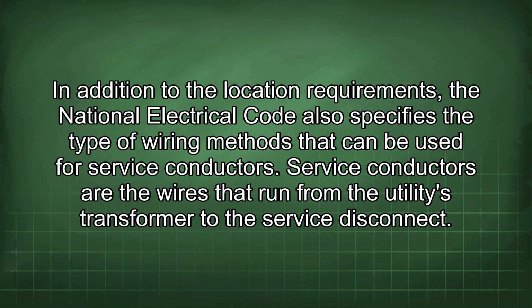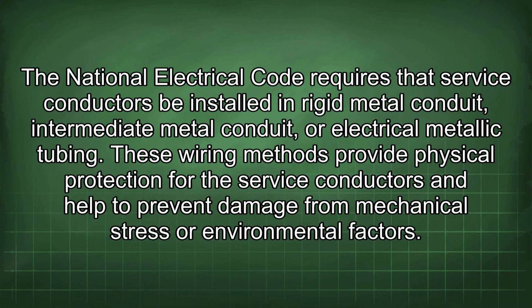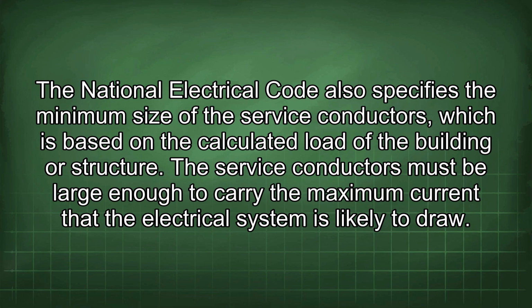Service conductors are the wires that run from the utilities transformer to the service disconnect. The National Electrical Code requires that service conductors be installed in rigid metal conduit, intermediate metal conduit, or electrical metallic tubing. These wiring methods provide physical protection for the service conductors and help to prevent damage from mechanical stress or environmental factors. The National Electrical Code also specifies the minimum size of the service conductors, which is based on the calculated load of the building or structure. The service conductors must be large enough to carry the maximum current that the electrical system is likely to draw.